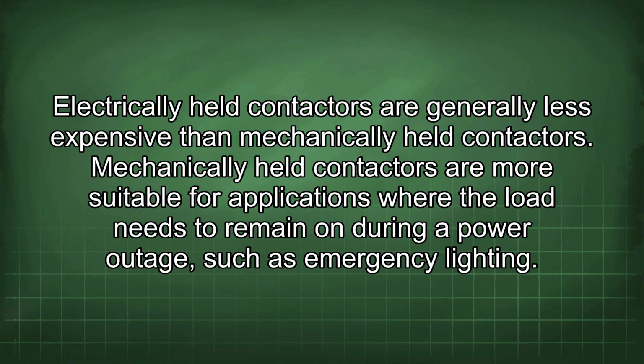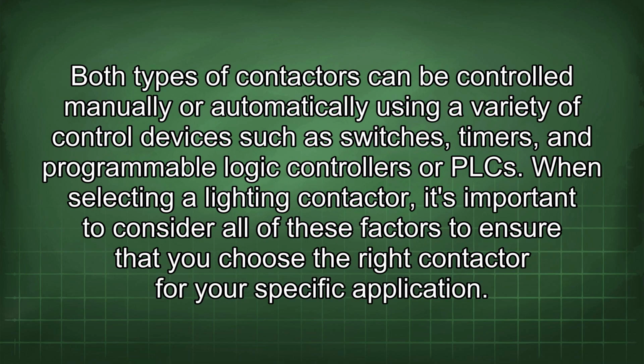Mechanically held contactors are more suitable for applications where the load needs to remain on during a power outage, such as emergency lighting. Both types of contactors can be controlled manually or automatically using a variety of control devices such as switches, timers, and programmable logic controllers or PLC. When selecting a lighting contactor, it's important to consider all of these factors to ensure that you choose the right contactor for your specific application.